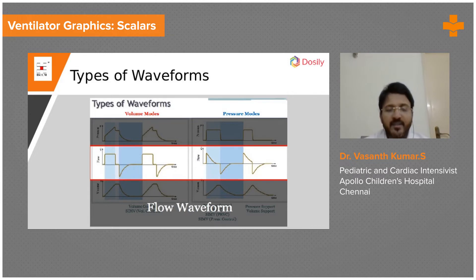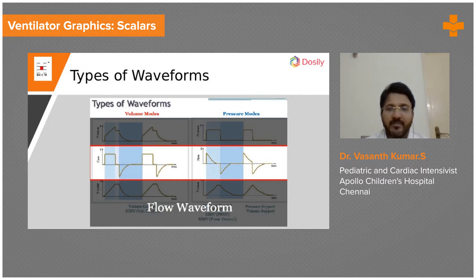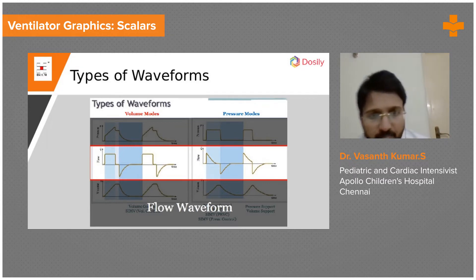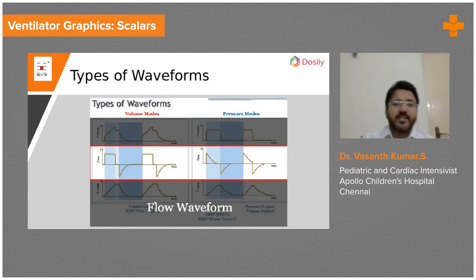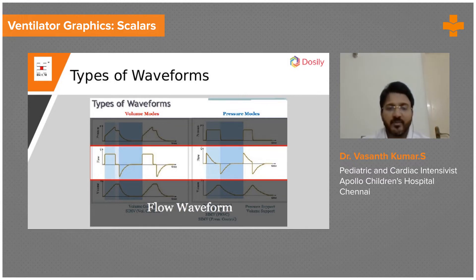The next is: whichever looks like a mountain is called the volume-time scalar. You can see this one is looking like a mountain — so this becomes the volume-time scalar. So to summarize: mountain shape is volume-time, and negative deflection is flow-time.